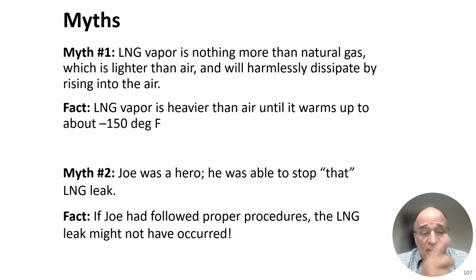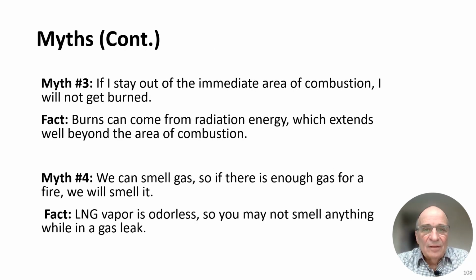Myth number two: Joe was a hero because he stopped that LNG leak. Quite often, if Joe had followed proper procedures, the LNG leak might not have occurred in the first place. Myth number three: if I stay out of the immediate area of combustion, I will not get burned. Burns can come from radiation energy, which extends well beyond the area of combustion.